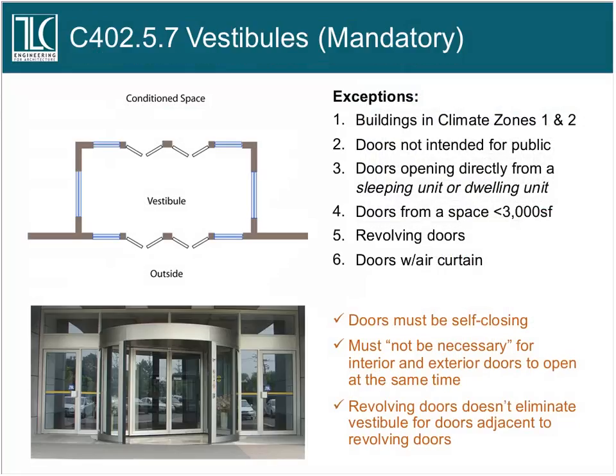And one of the most significant ones of these is a mandatory requirement for vestibules, except in climates 1 and 2. So any of the primary entrances to the building must have a vestibule, and it must be deep enough that it's not necessary for both the interior and exterior doors to be open at the same time in order to get through the space. I've talked once again to a lot of building designers that say, oh my gosh, I'm going to have to give up floor space in my building entrance to accommodate this vestibule. This is not something I was counting on. And once again, because it's mandatory, you can't use an energy model to get out of it.